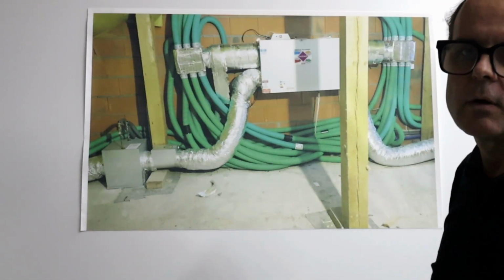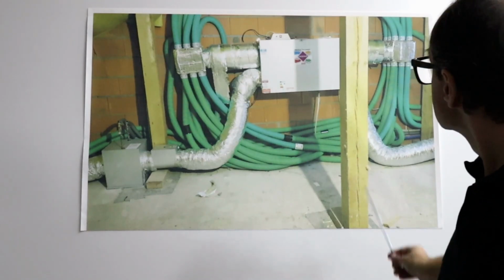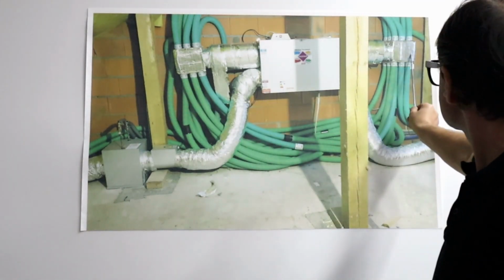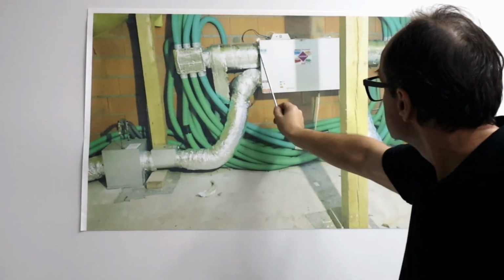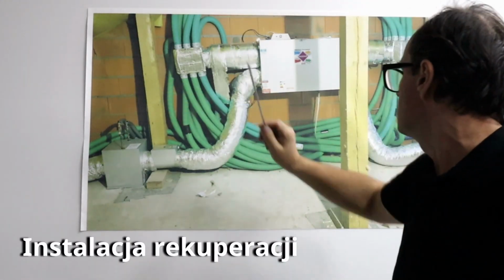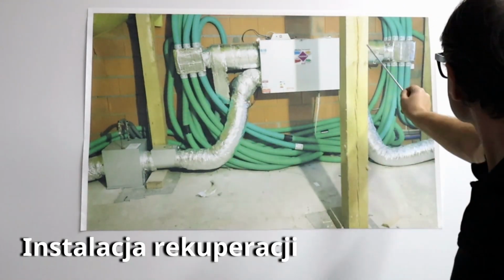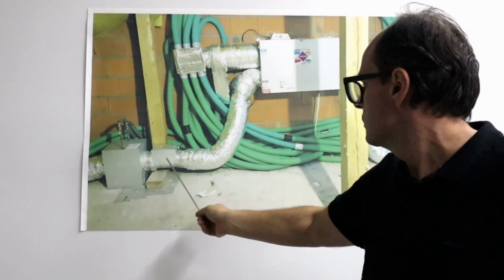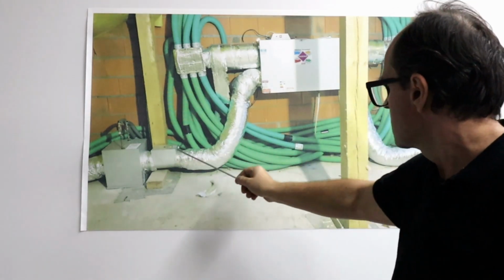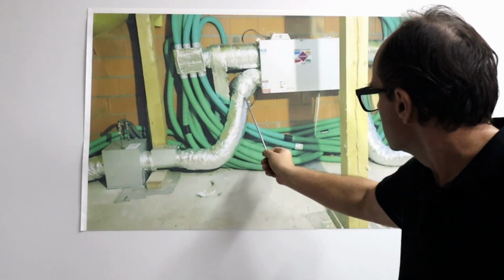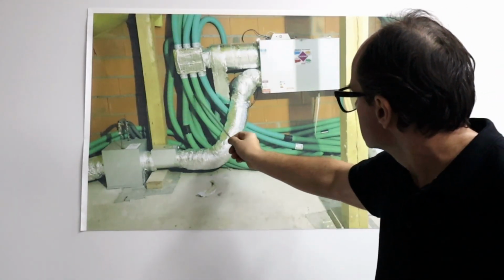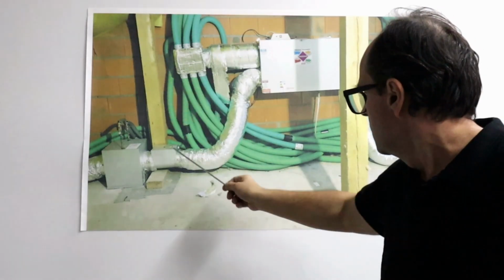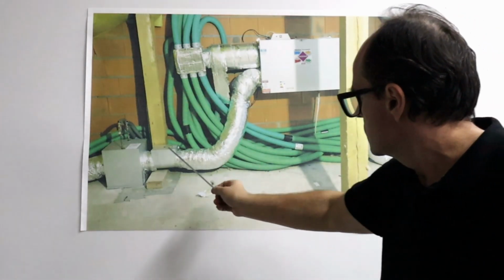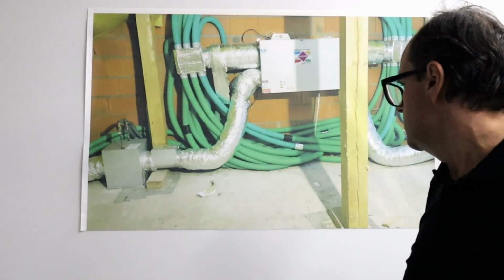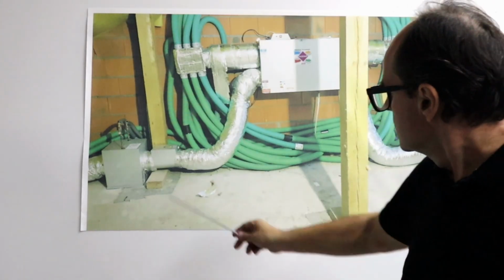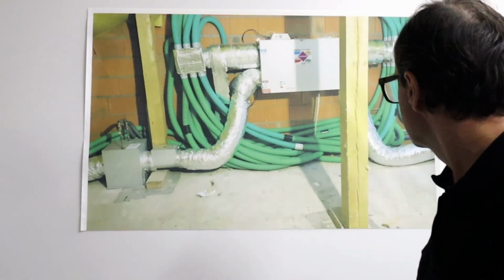And this so-called expert ran away from the construction site, won't fix it, won't even talk to the client. So here I've given you an example of how not to do an electrical installation. Remember, there must be space here for a short section of thermally insulated flexible duct for dampening, because we have a lot of noise here, same here. Remember, never ever mount a heater on wooden elements. The heater should be placed about a meter or 80 centimeters away from the unit. It also shouldn't touch plastic ducts, because at some point this protection might stop working, something might happen. Although our PTC heaters have two thermal protections, this is also installed incorrectly.